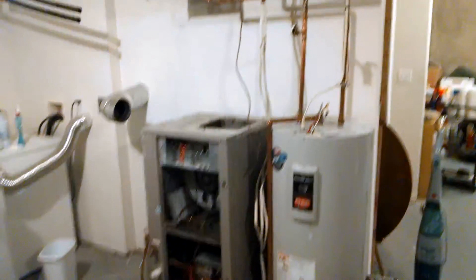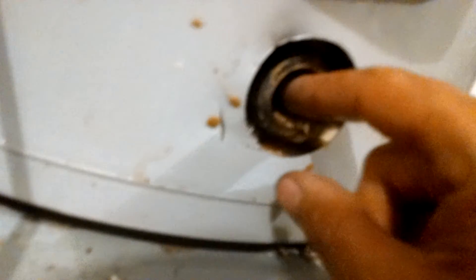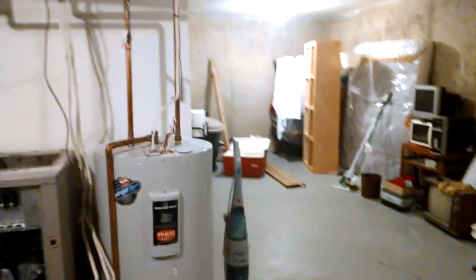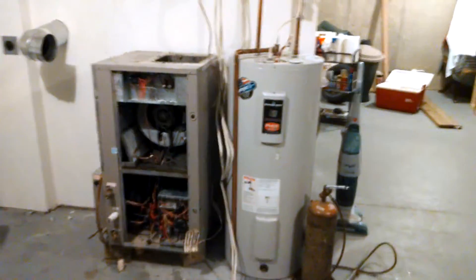I've removed everything. Working on the desuperheater stuff, I was pulling the bottom drain off — and this is the importance of looking beyond what you're actually doing. This unit is full of slag; it has probably never been drained. It's full of that white stuff you see there.